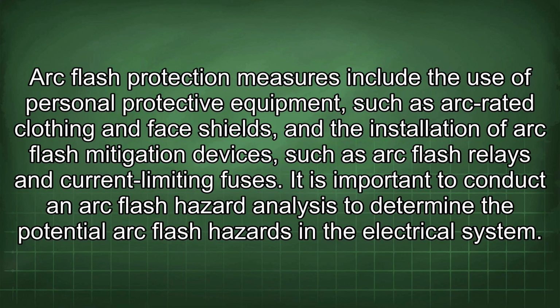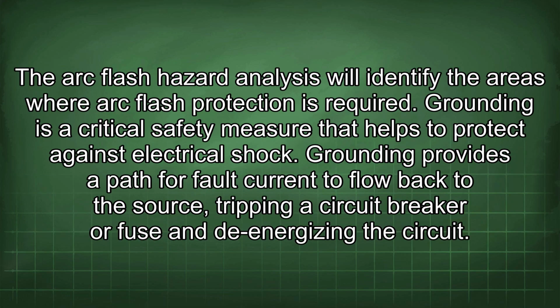Arc flash protection measures include the use of personal protective equipment, such as arc-rated clothing and face shields, and the installation of arc flash mitigation devices, such as arc flash relays and current-limiting fuses. It is important to conduct an arc flash hazard analysis to determine the potential arc flash hazards in the electrical system. The arc flash hazard analysis will identify the areas where arc flash protection is required.